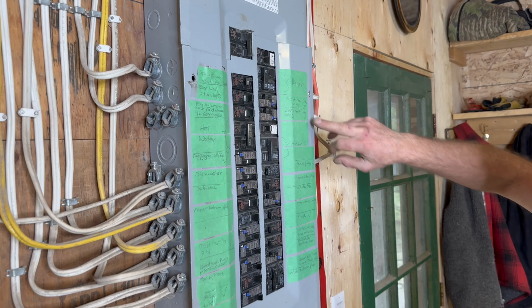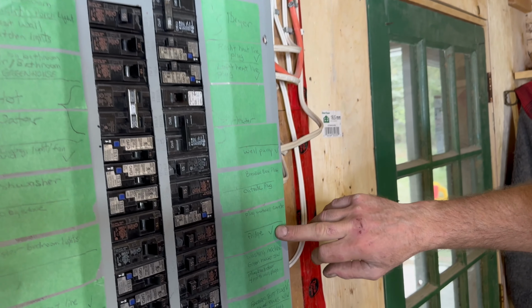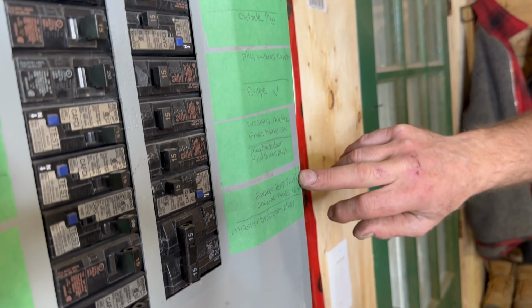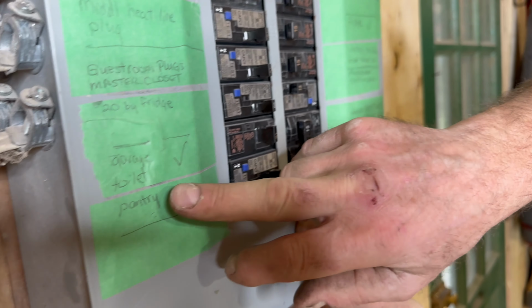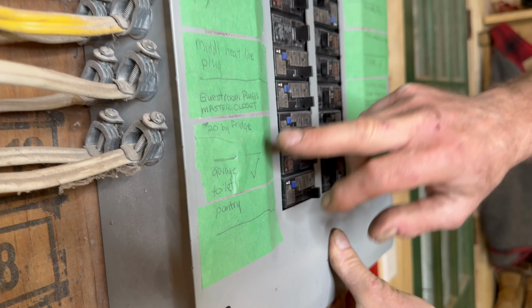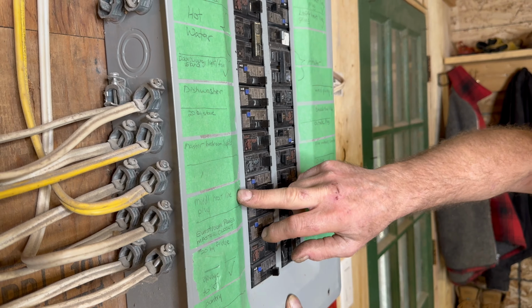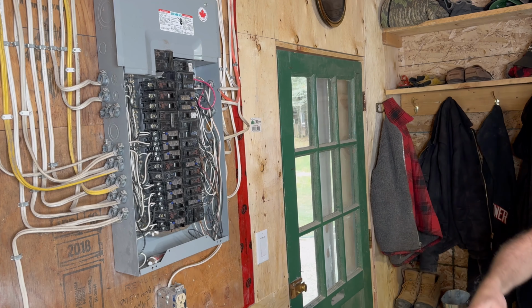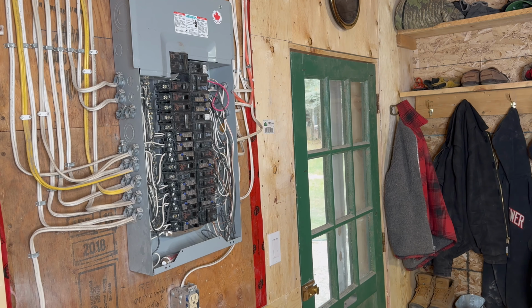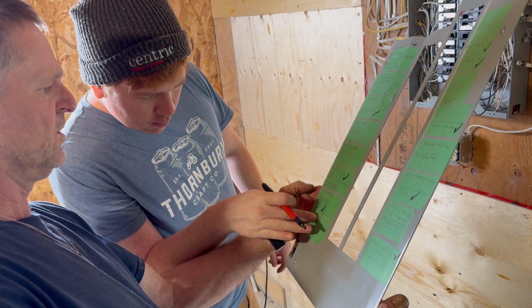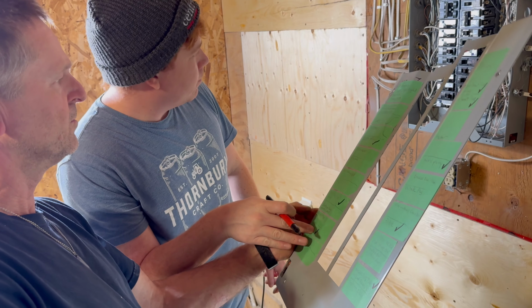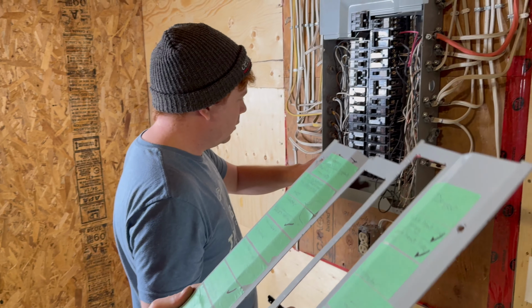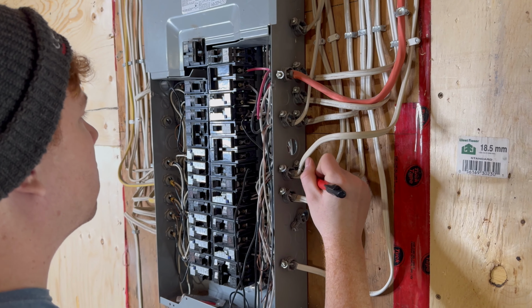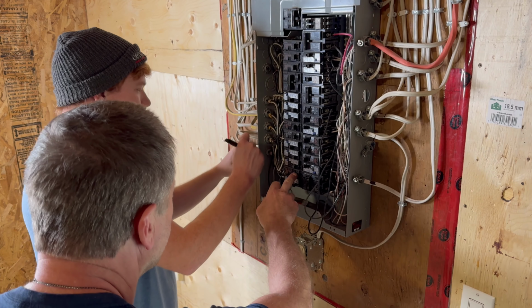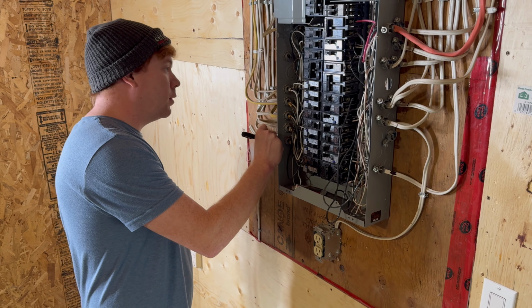Begin by determining which essential circuits you'd like to be able to power with your generator during an outage. Here Brad has labeled all existing circuits, but marked those essential circuits with a check mark. Start work by switching off the main breaker, then removing the access panel so you can get at the circuit breakers. Here Brad is explaining to Mark which circuits he wants powered during an outage, and Mark is labeling individual cables so he knows which ones to reroute into the manual transfer switch.